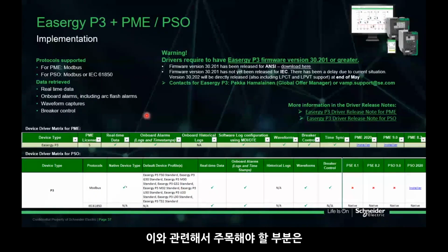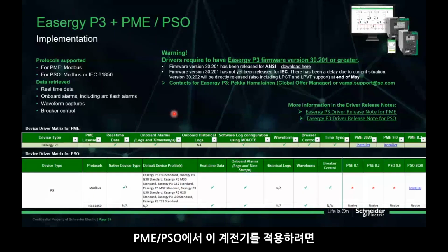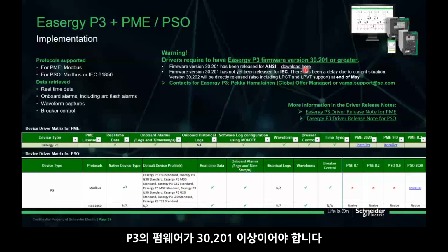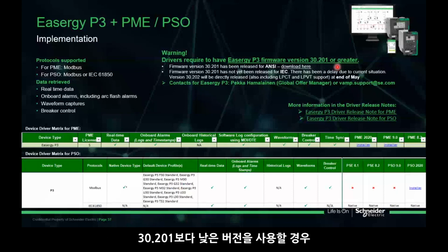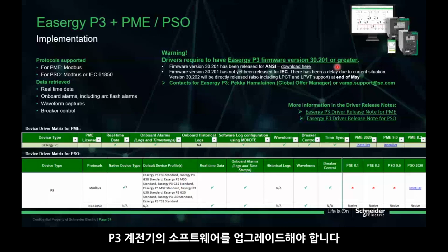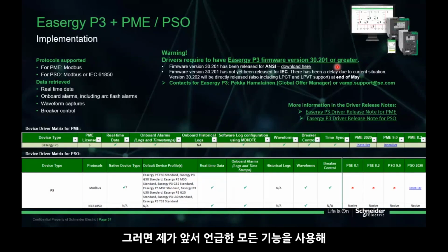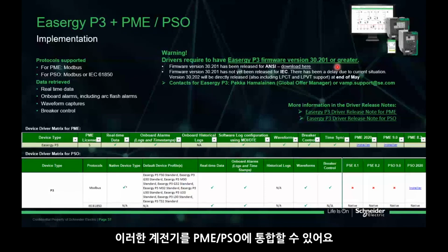One thing to take note of is the firmware of the relays. If you want to apply this relay into PME PSO, make sure the firmware of the P3 is 30.201 or greater. If you have a version smaller than that, you need to upgrade the firmware of the P3 relays. Then you will be able to integrate this relay into PME PSO with all the functionality I mentioned earlier.